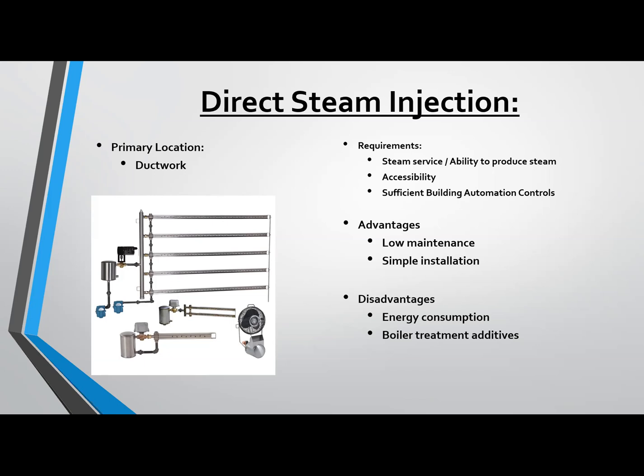Advantages to direct steam injection: low maintenance. Preventive maintenance on these systems is usually a once-a-year check, clean the nozzles, check for clogs, everything. Since it's tied into a building automation control system, there's a lot of data to be trended. You can see when the equipment is operating optimally or when it is not, and maintenance on these is pretty low. It's a fairly simple installation.